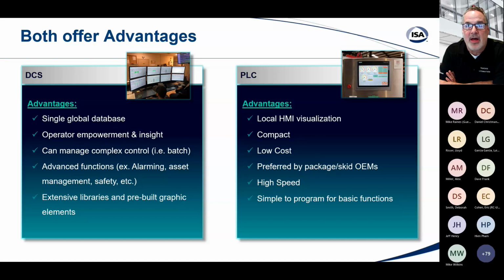Take, for example, one of the early plants I ever worked on, we were using a hybrid system, and we had 5 operator screens, different stations. If one operator acknowledged an alarm on one screen, the other screens didn't know that alarm was acknowledged. So we had to go in there and tie that together manually. On a single global database, if you have 30, 40, it doesn't matter how many screens in different building units or whatever, if one screen acknowledges that alarm, all the other screens will recognize that alarm has been acknowledged.